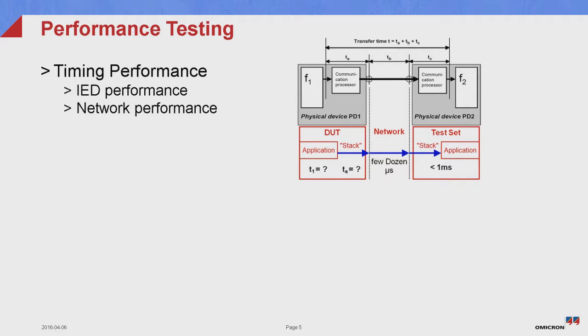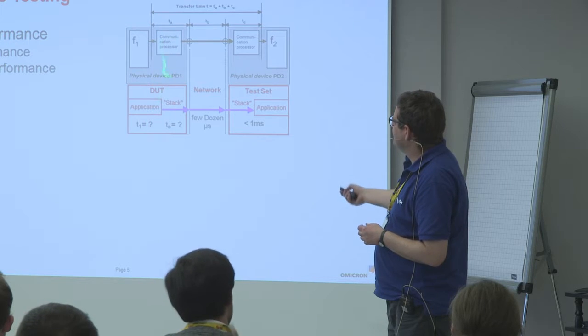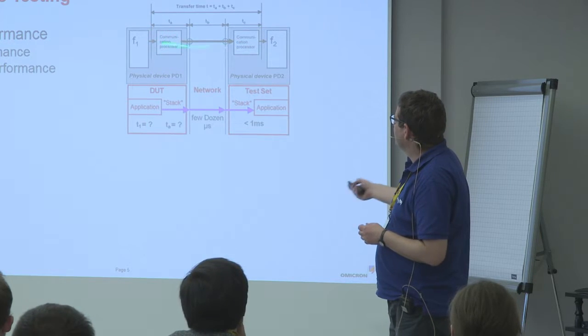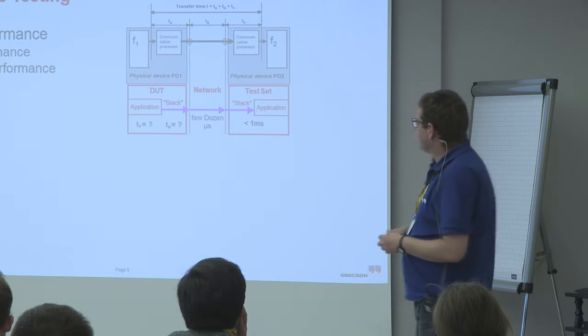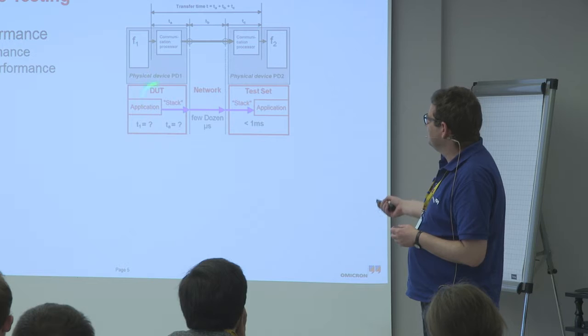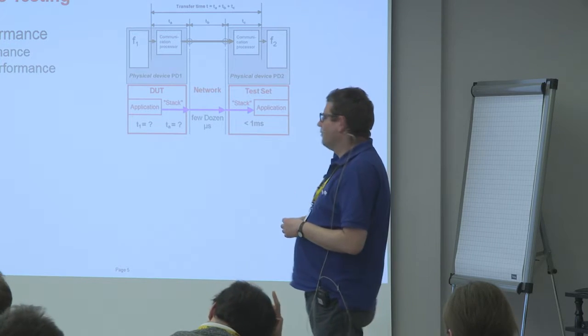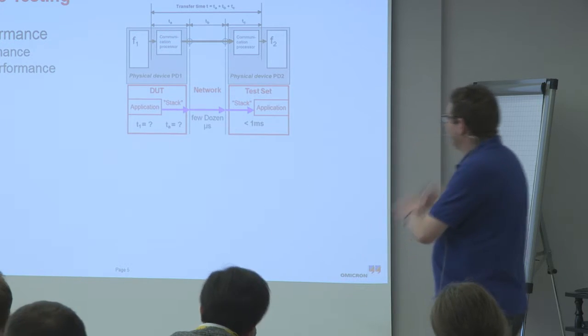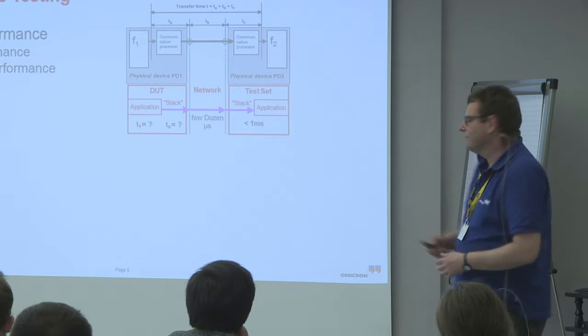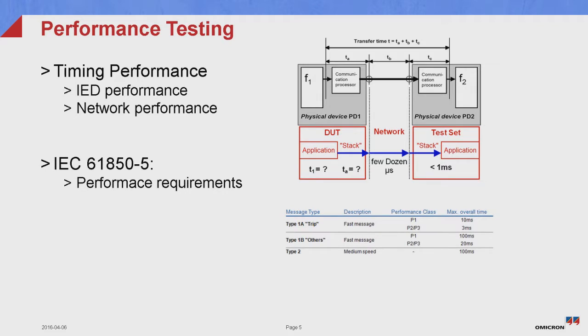The standard defines some requirements for what has to be done regarding performance: how fast functionalities and communication should be. You see here we have two devices, they have a communication stack inside, and they are communicating together, and there is some time that we need for that. The application will need some time, the stack itself, then the network, which we have already been talking about, and you will see later how long it takes to transmit information. And when we also perform the test with a test set, then we also have its own time inside.